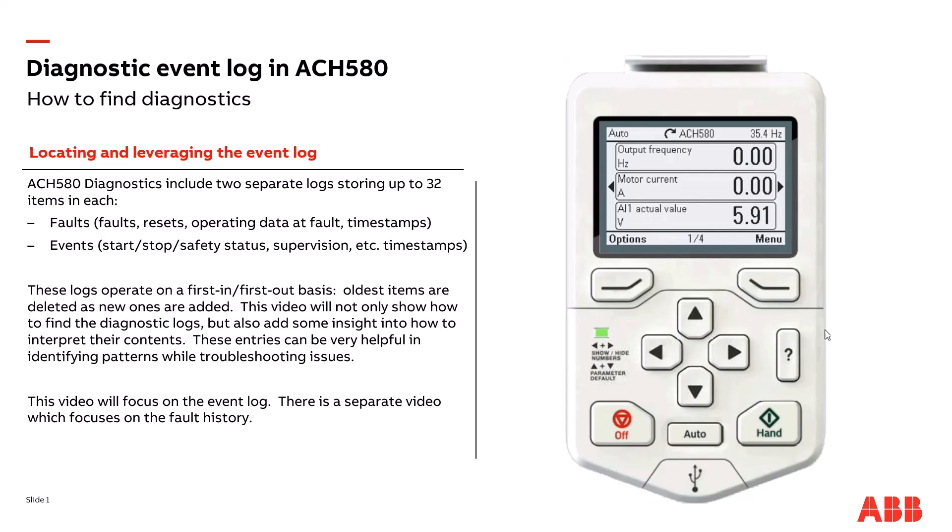Hi, this is Jeff Brunner. I'm a member of the ABB HVACR Application Engineering team. In this video, I'd like to introduce the enhanced diagnostic capabilities of the ACH580. There are two separate log histories maintained in the drive, each capable of storing up to 32 entries, and these operate on a first-in, first-out basis, so once at capacity the oldest items are deleted first and the new ones are added.